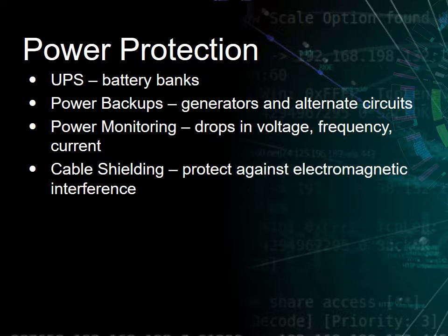provides enough power. So you need to take into consideration what all the things are that you want to run off those generators. Do you want just your data center? Well, guess what? That data center also requires things such as air conditioning and climate control. Those systems take a lot of power. You might not put those systems on the UPS because you can last maybe 15 minutes without your air conditioning or the humidity control in the data center. However, if you're going into hours of needing to be on a generator, you need to make sure that all the things that support your IT also are added to that generator.